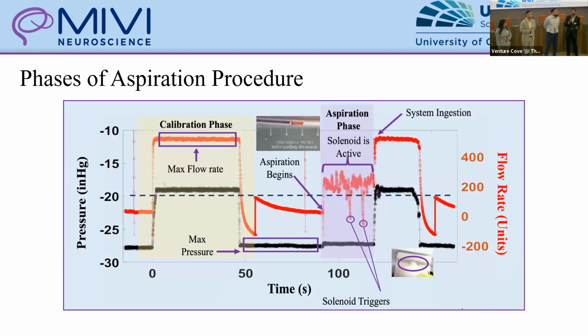So one of the key components to achieve our objective of reducing clot aspiration time is our custom trial procedure. Now, our procedure consists of 2 phases, the calibration phase and the clot aspiration phase. The calibration phase calculates the max flow rate and pressure regardless of the catheter system configuration. The clot aspiration phase is what our algorithm actually acts upon. We define specific thresholds during the calibration phase, and if the flow rate drops below those thresholds, we will actuate a solenoid valve. The key purpose of this is to reduce the system ingestion time, which we define as the time it takes for the clot to be ingested into the collection canister.